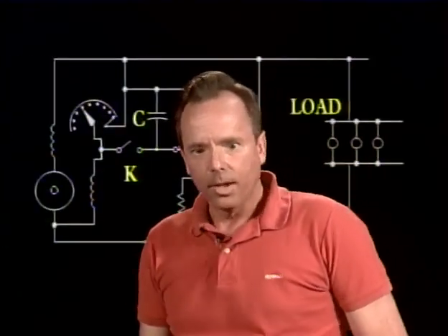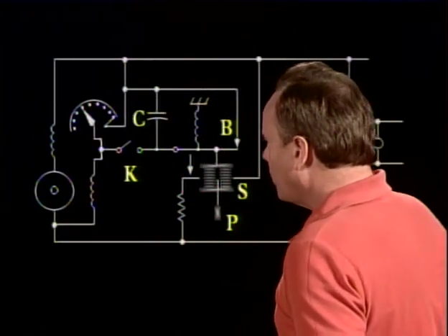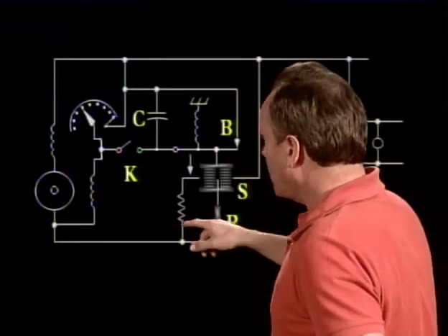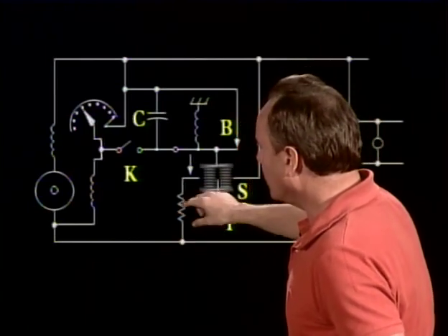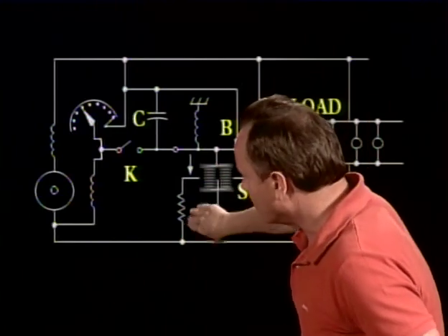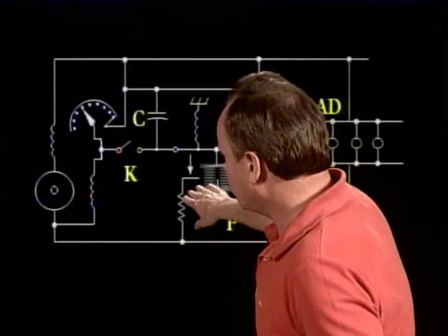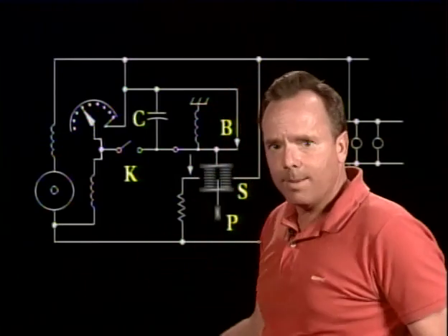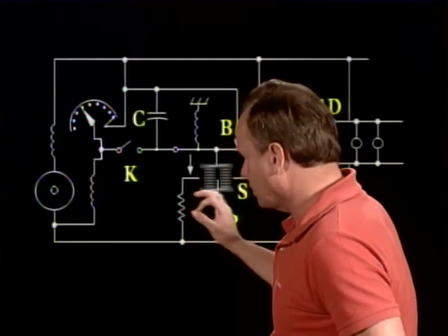How about that? All right, let's take a look at how you regulate the voltage of a generator. Now, here is a schematic of a voltage regulator, and essentially what you do is you change the amount of current that goes through the field. The way you change the amount of current that goes through the field is you change the resistance in the circuit for the field, by inserting resistance or taking resistance away. In fact, what you have is a little vibrating device that alternately puts this resistor in or out of the circuit, and the more that the resistance is in the circuit, the lower the field voltage and the lower the output of the generator. And it vibrates back and forth, and on average it keeps the right voltage in the field and therefore gets the right output of the generator. So a voltage regulator controls generator output voltage by changing the resistance of the generator field circuit, which varies the current flow to the generator field coil.